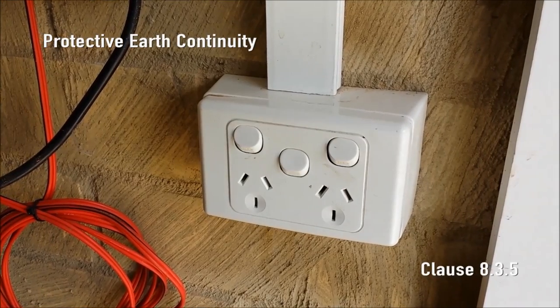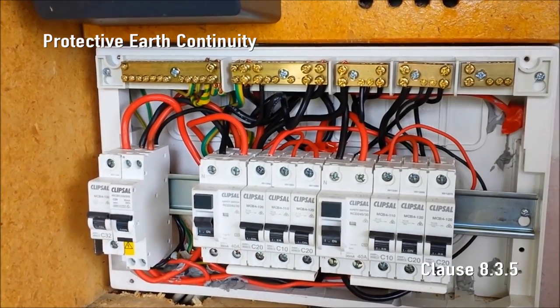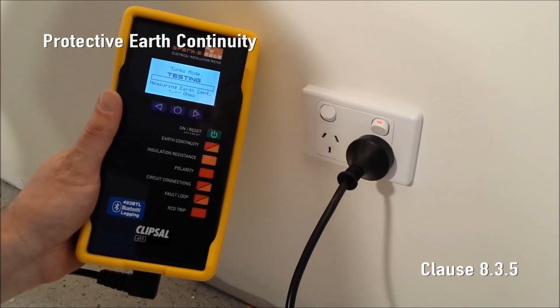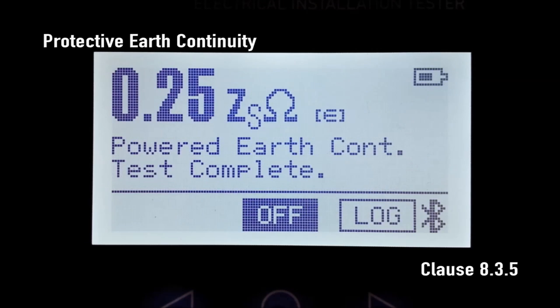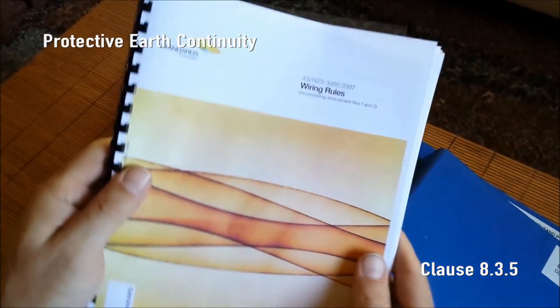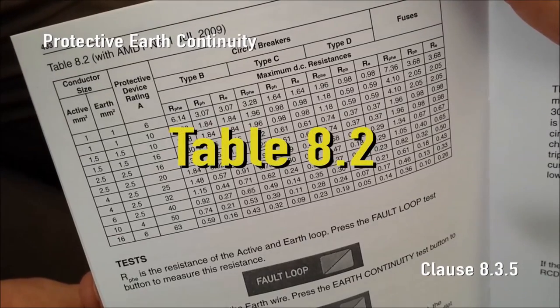Protective Earth Continuity. Every socket outlet and every non-double insulated lighting fixture requires a protective earthing conductor to be bonded to the neutral at the MEN connection in the main switchboard. Simply plug SparkyMate into a live socket outlet and press earth continuity. SparkyMate uses the neutral conductor as a probe lead to measure and display the resistance of just the protective earthing conductor. The maximum allowable resistance depends on the protective device — refer to AS/NZS 3000:2007 with amendment 1 July 2009 and check table 8.2, which is also in the 493 series handbook.